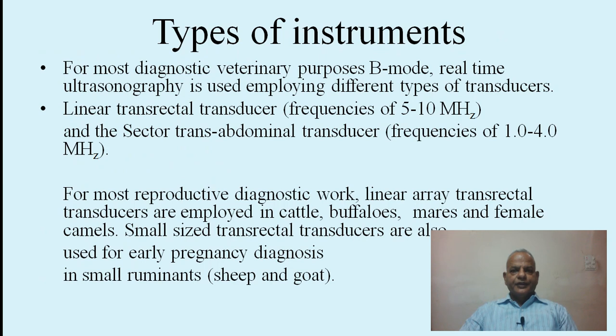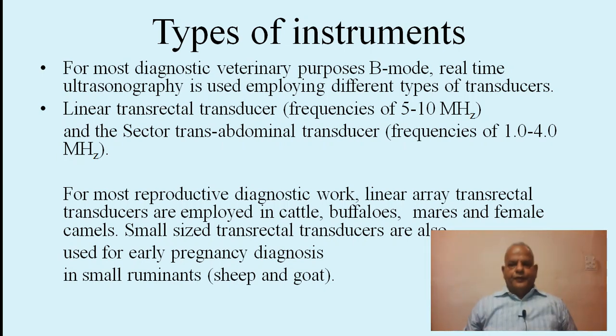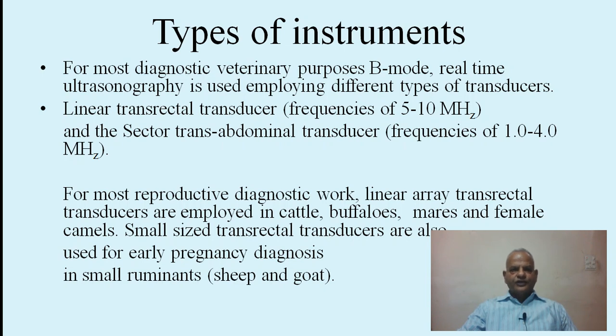For most diagnostic veterinary purposes, B-mode real-time ultrasonography is used, employing different types of transducers: the linear transrectal transducer with frequencies of 5 to 10 MHz, and the sector transabdominal transducer with frequencies of 1 to 4 MHz. For most reproductive diagnostic work, linear array transrectal transducers are employed in cattle, buffaloes, mares, and female camels.